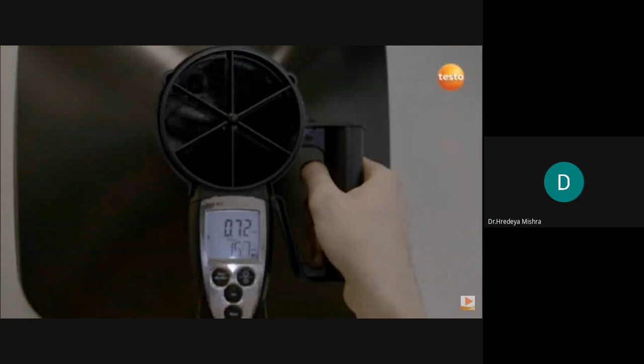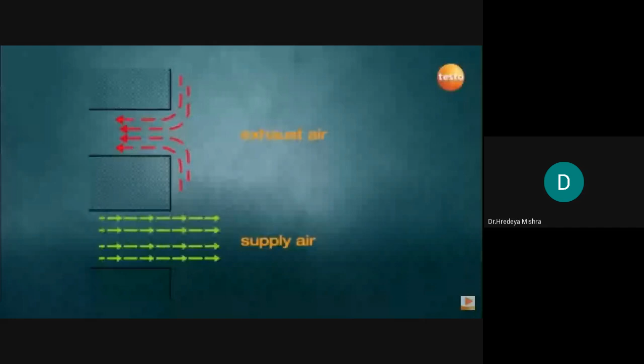This is how you measure properly at the exhaust air outlet. A funnel is required to measure the exhaust air. The reason? There is no directed flow profile available for exhaust air as the air is sucked in funnel-like from the room. This means there is no definable area in the room via which the volume flow can be determined. This challenge is easily solved with the aid of the Testo 417 funnel, because the funnel creates defined flow conditions at some distance from the plate outlet in a fixed cross-section.